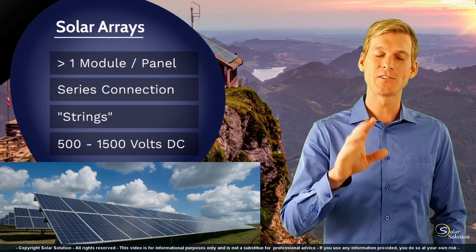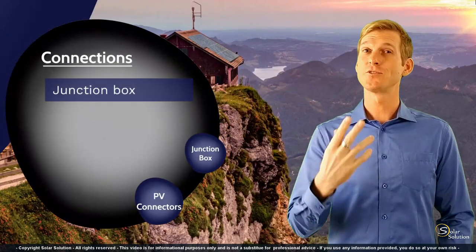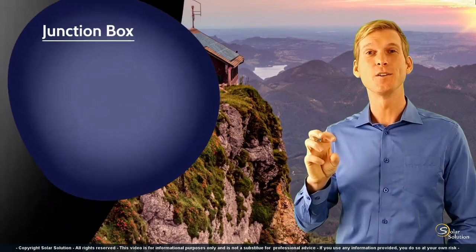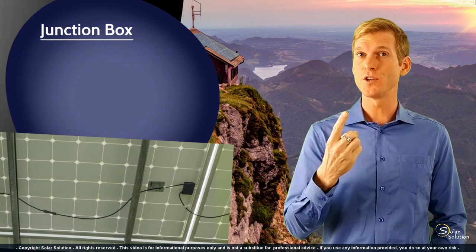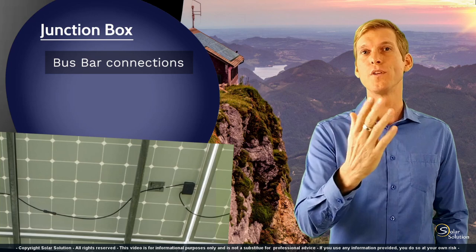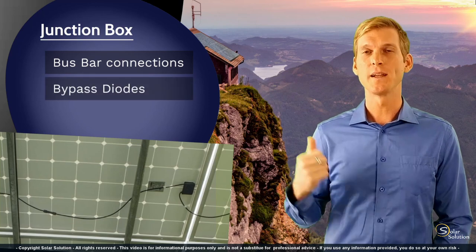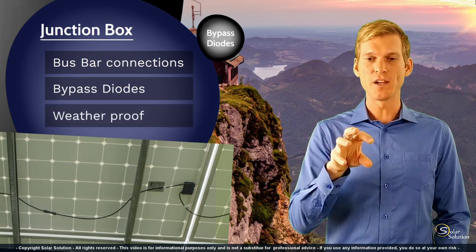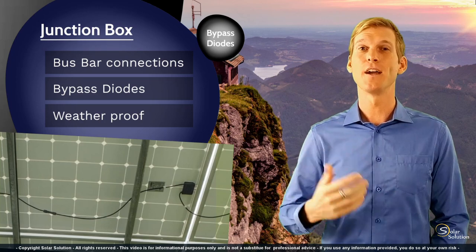Now let's look at the last section: connections — specifically junction boxes and external connectors. Junction boxes are the plastic black boxes glued to the back side of solar panels, attached to the backing sheet, and they have three functions. First, they connect the external wiring with the bus bars coming from all the solar cells on the front. Second, they contain the bypass diodes. Third, they are weatherproof — they ensure there's no connection between the internal electrical components and the outside environment.